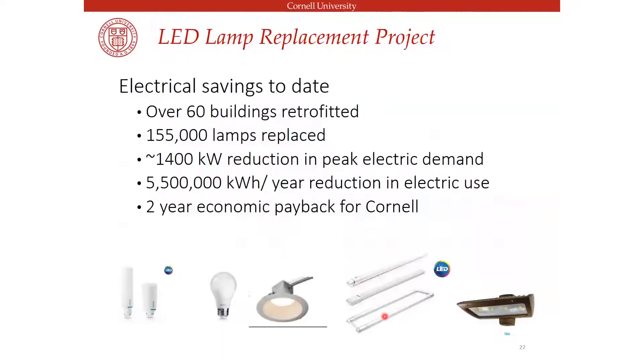A fun example of an energy conservation initiative project: we recently relamped almost the entire campus, replacing existing incandescents and CFLs with LEDs — more than 60 buildings, 155,000 lamps, and a more than 5 million kilowatt-hour per year reduction in electric use. We also have five solar farms online; each generates about 3 million kilowatt hours per year of electricity. The LED relamping has a two-year economic payback for Cornell, well within our 15-year target.